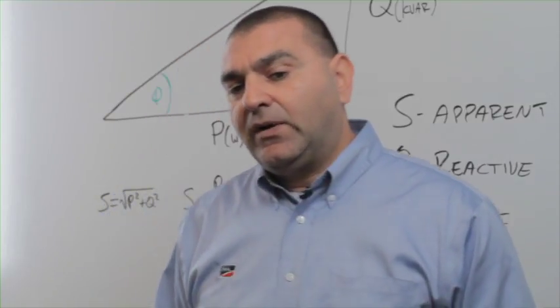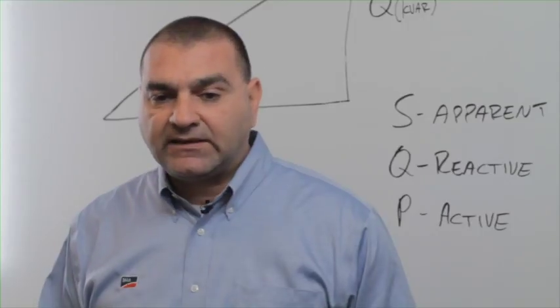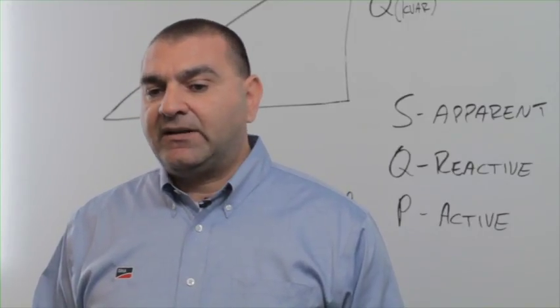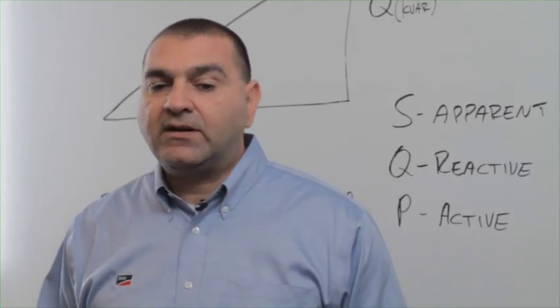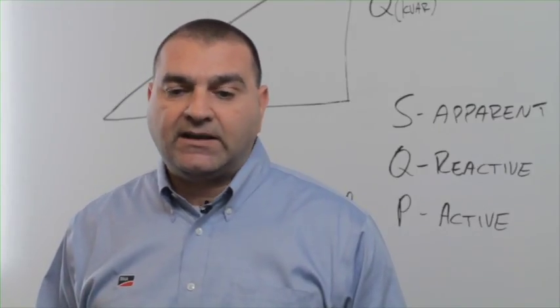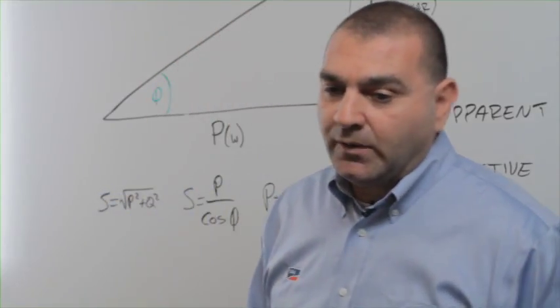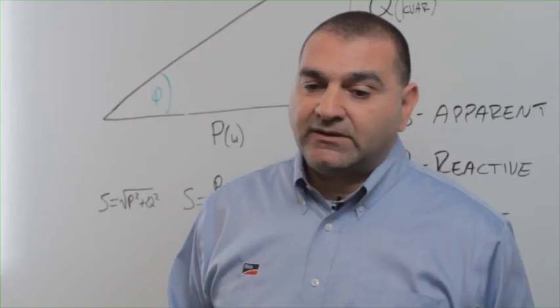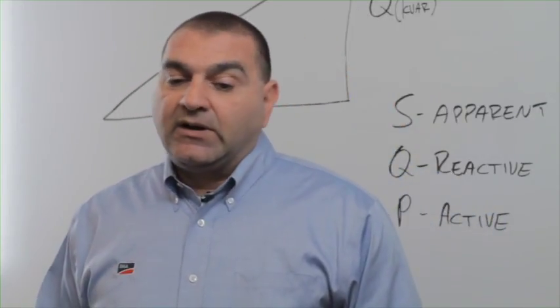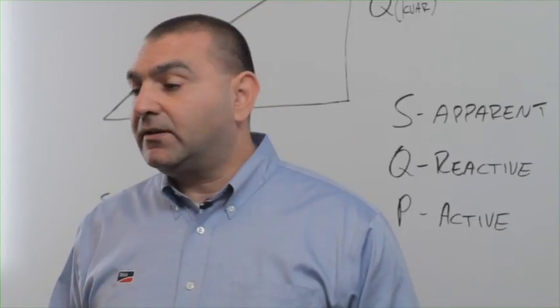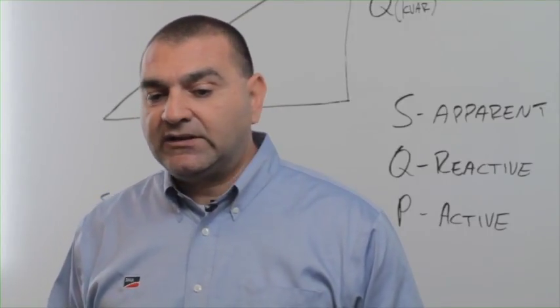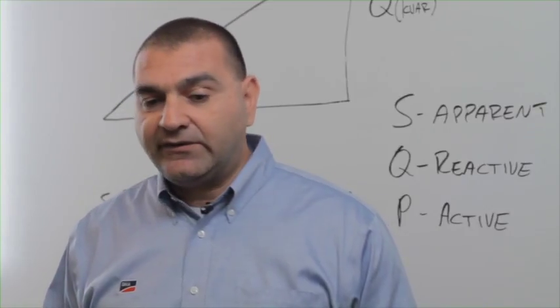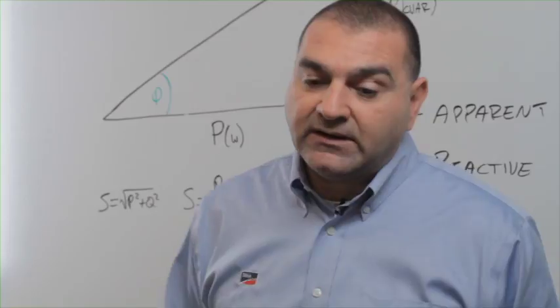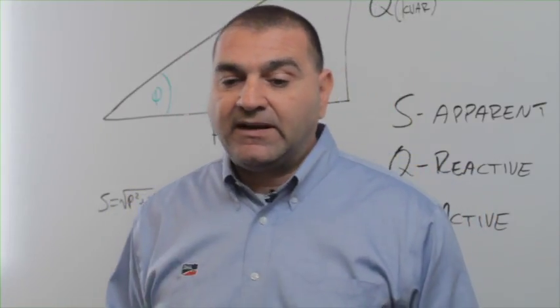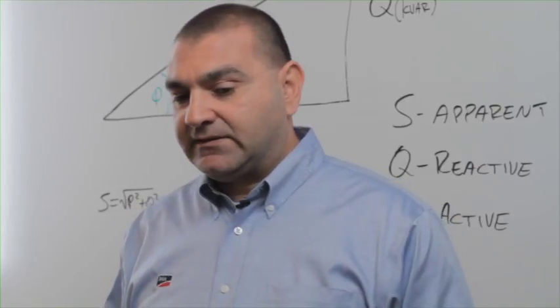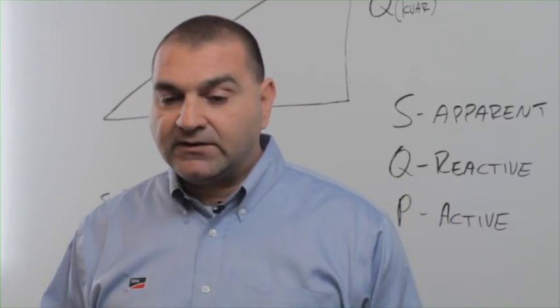So at SMA, we have developed certain grid integrated features that are summarized on the slide, and basically talks about the ability to dispatch the power of an inverter at different power rating levels. Also, our inverters are equipped with over-frequency automatic response, and we'll talk a little bit more about this feature in the next few slides. And we also are able to supply reactive power and operate the inverter in a power factor control mode, in addition to complying with FERC Order 661-A for voltage ride-through. And because of our German requirements, we are also able to supply reactive current during fault ride-through, something that's not required in North America, but it's a nice feature in helping recovery from voltage dips.